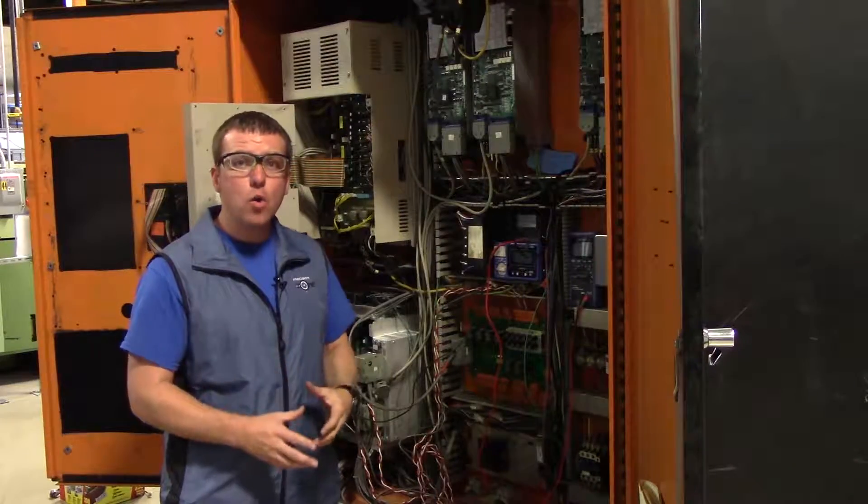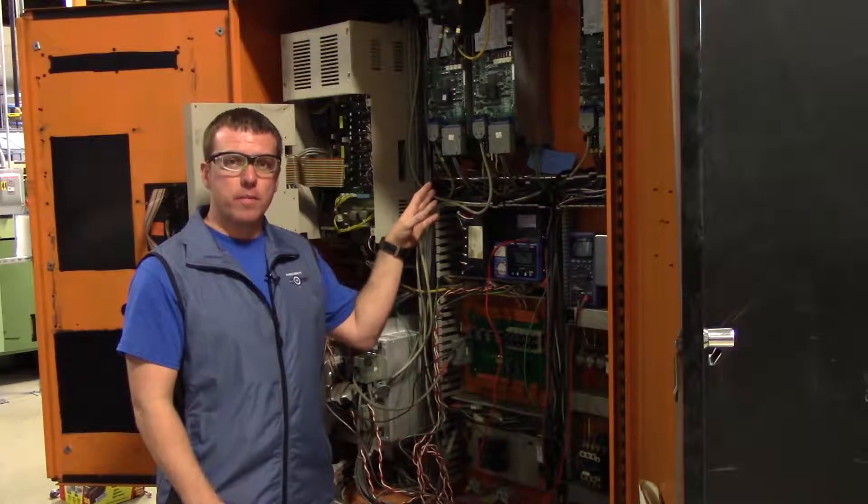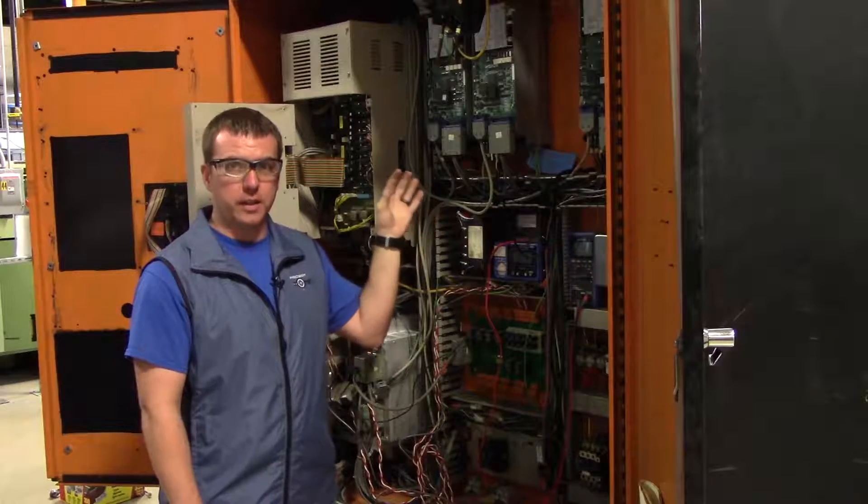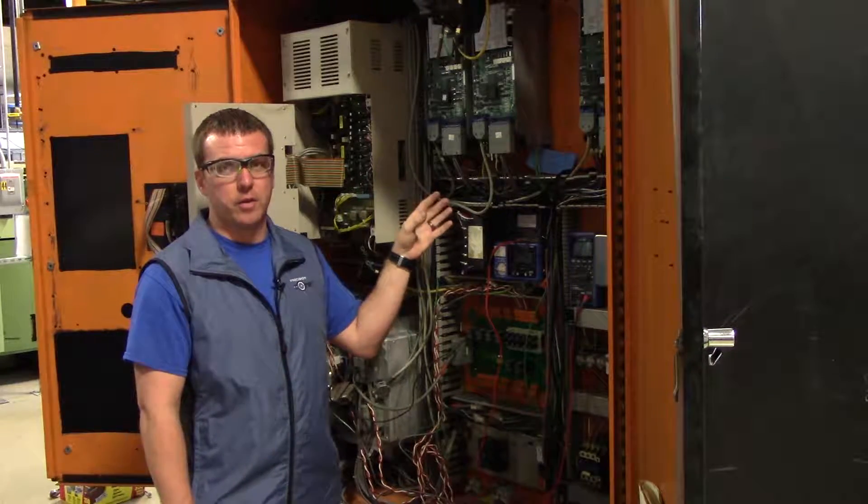So we know we have a problem from the winding selector contactor up to the motor. All six leads are grounded, so that will definitely have to be replaced.